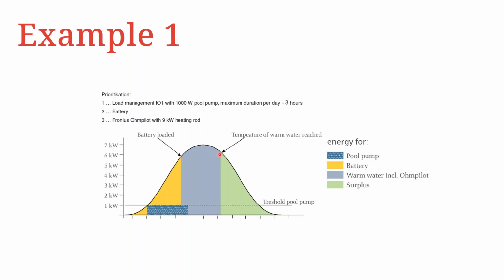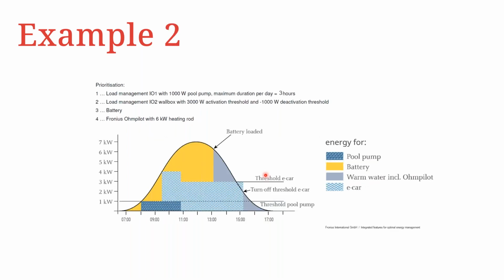You can see that even with this kind of prioritization and load management, we still have quite a bit of excess energy available, which you can see here in green. This means that this is power that would most likely sit idle on the roof, because like I said, in most African countries, we are not allowed to sell this portion of power to the grid. So it means that you are losing quite a bit of PV production there. Example number 2 tries to take care of that, and we have several combinations here.